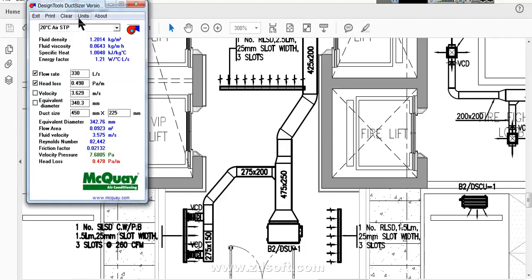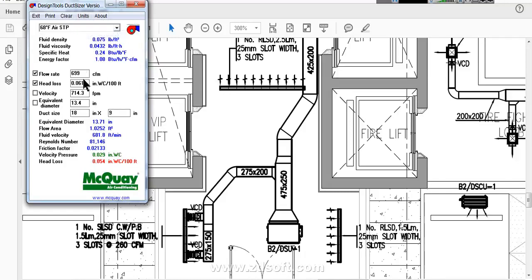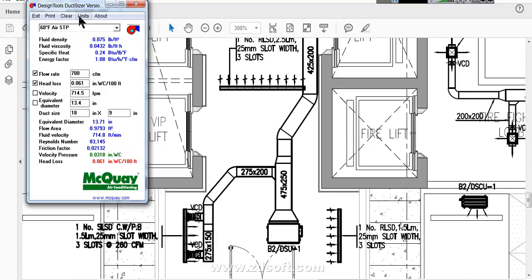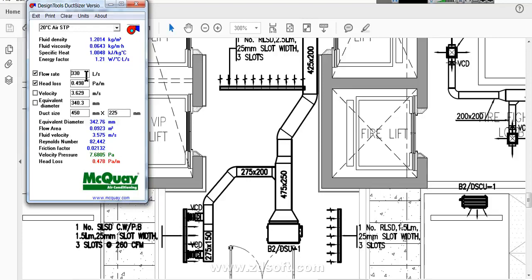So we will open our software. Here we need to change our unit because this is liters per second. We need to go to another unit. Here we will enter 700 CFM. And we will go back again to liters per second, because 700 CFM is equivalent to 330 liters per second. The ratio is 2.1. You know this multiplied by 2.1, it will go to CFM.